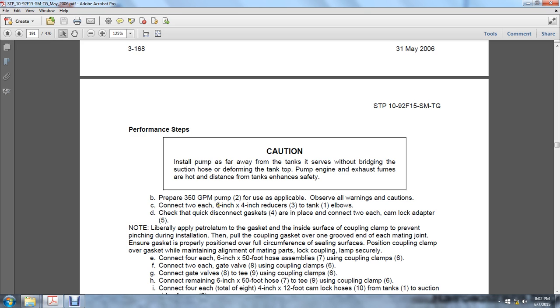Connect two, each, 6-inch by 4-inch reducers 3 to the tank elbows. Check that the 2 quick disconnect gaskets are placed in the 2 connecting camlock adapters 5. Liberally apply petrolatum to the gasket and the inside surface of the coupling clamp, preventing pinching during installation. Then pull the coupling gasket over one of the groove ends of each mating joint. Ensure the gasket is properly positioned over the full circumference of the sealing surface. Position the coupling clamp over the gasket while maintaining alignment with the mating parts, locking the clamp securely.